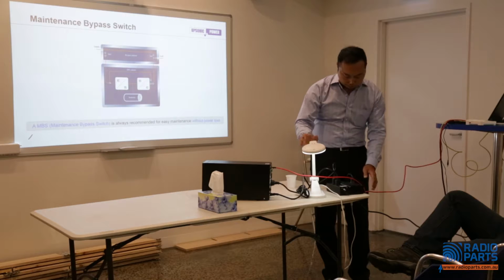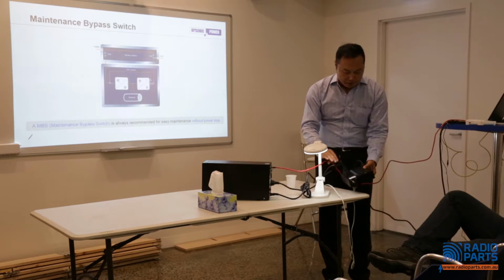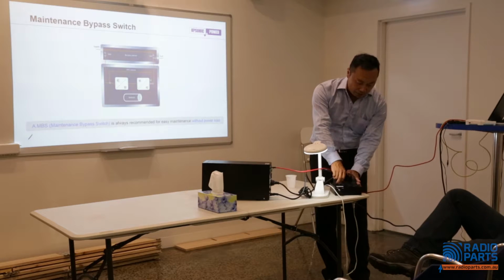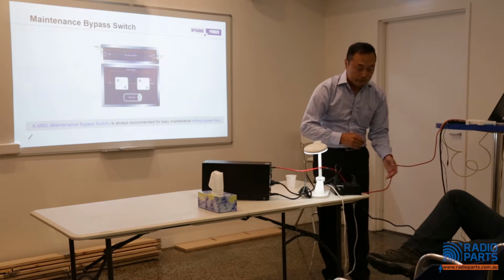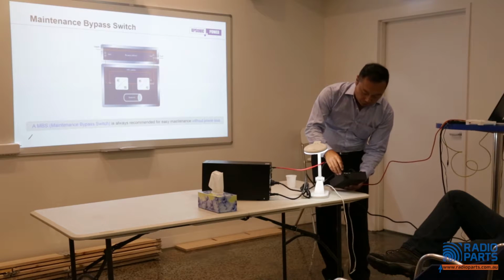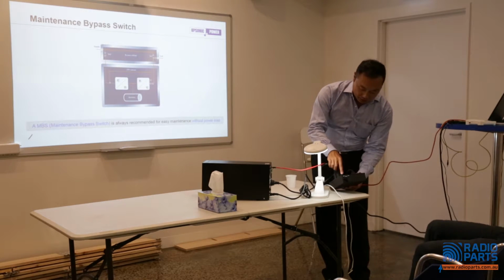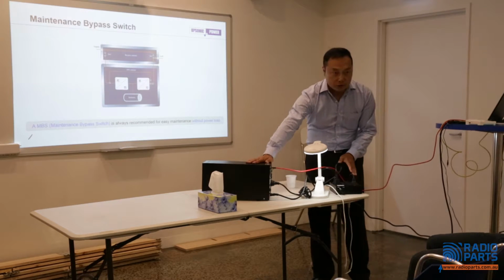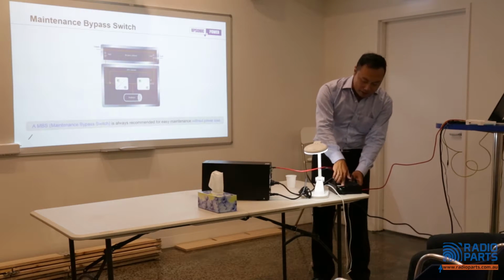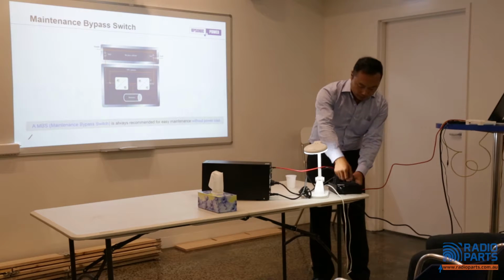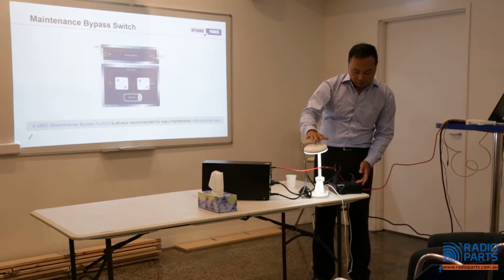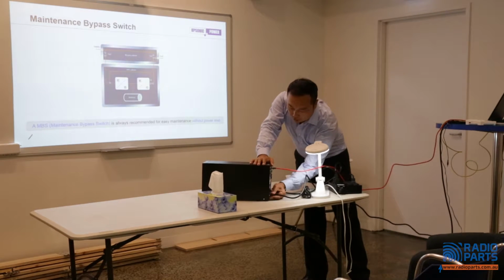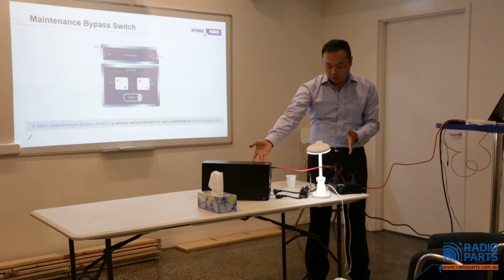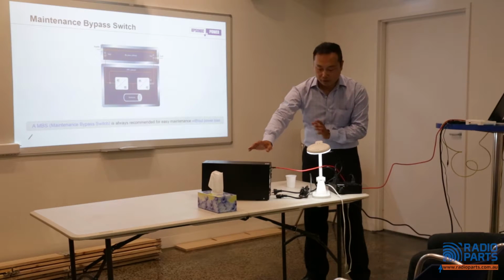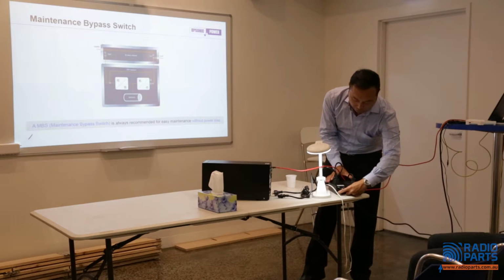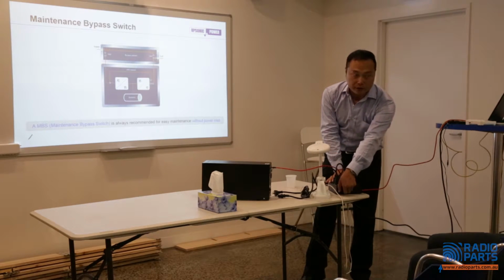Now here's our load, and this is a small maintenance bypass switch. That's desktop type, which also comes like a rack mount type, and it has 2 modes: normal mode and bypass mode. Now it's in normal, which means the power comes from the UPS. If we turn it to bypass, it will bypass the UPS, and you don't lose power. And we can just take this out. And of course, if we turn it to normal, it's off because there's no power coming from the UPS.